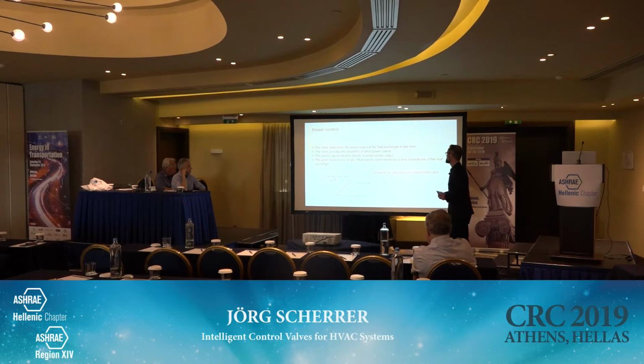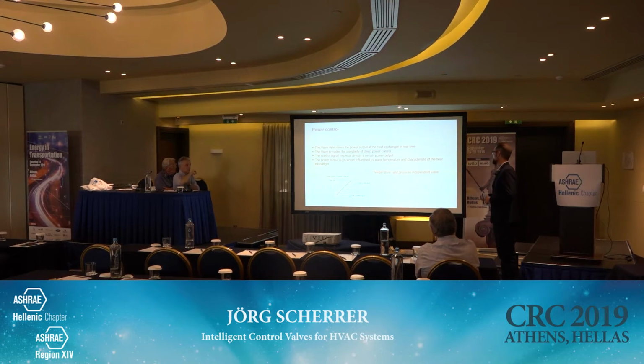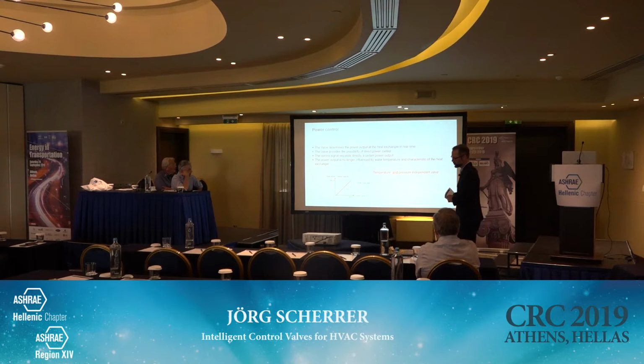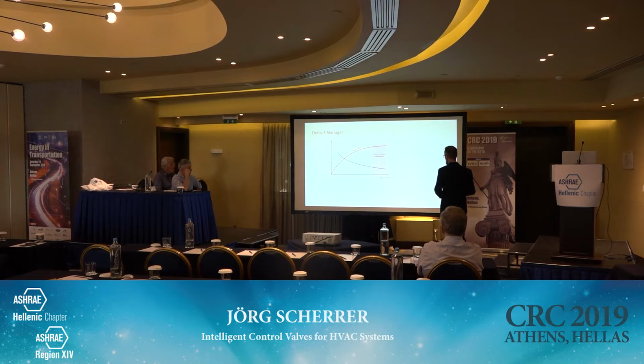The valve determines the power output at the heat exchanger in real time, and the power output at the heat exchanger is no longer influenced by water temperature and characteristic of the heat exchanger. This is one feature of modern control valves we are able to do now to avoid problems on the heat exchanger. The second feature is delta T management. Delta T management, we see here this characteristic.